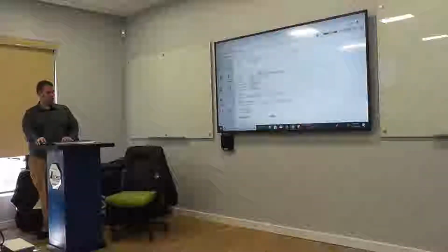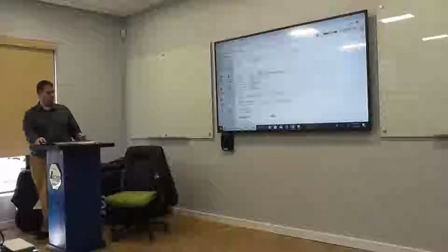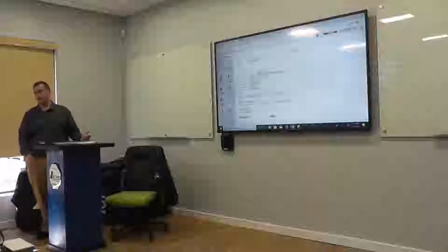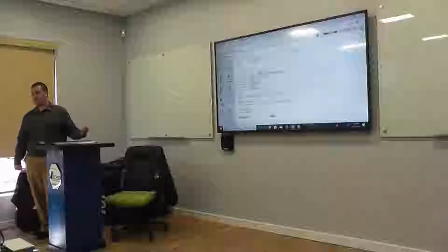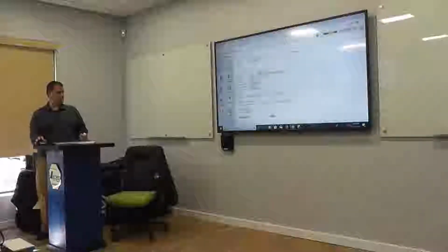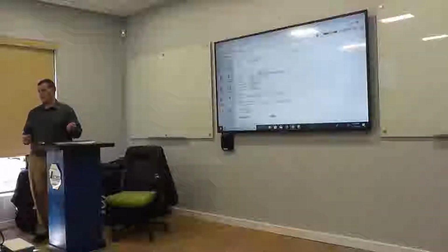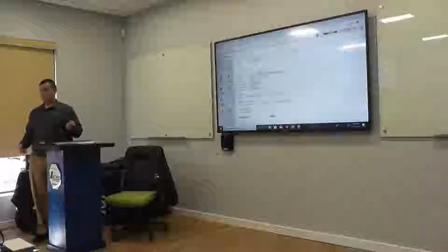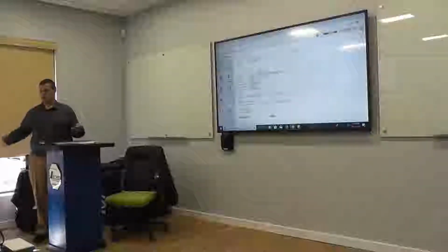So down here is the double card presentation. This is where you would assign that double card access to the access level. So it would get assigned to the access level, and then you could define a max unlock time if you wanted to. If there's not a time defined, then that reader's going to stay unlocked until you lock it. It's handy a lot of times where maybe you have rooms, conference rooms or classrooms, you want it to unlock for the teacher: they come in, they scan the door, unlock the door.